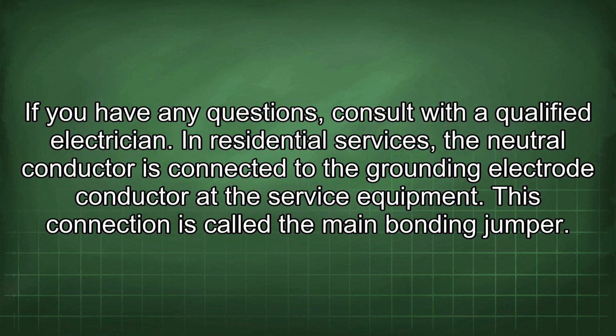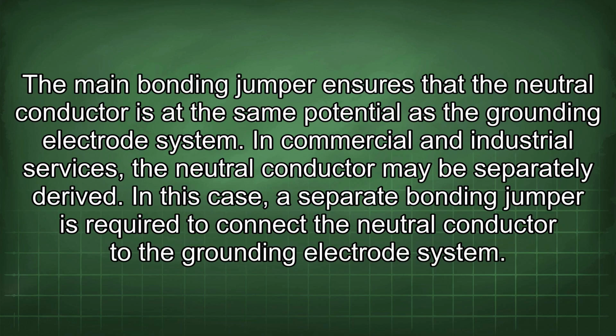In residential services, the neutral conductor is connected to the grounding electrode conductor at the service equipment. This connection is called the main bonding jumper. The main bonding jumper ensures that the neutral conductor is at the same potential as the grounding electrode system. In commercial and industrial services, the neutral conductor may be separately derived. In this case, a separate bonding jumper is required to connect the neutral conductor to the grounding electrode system.